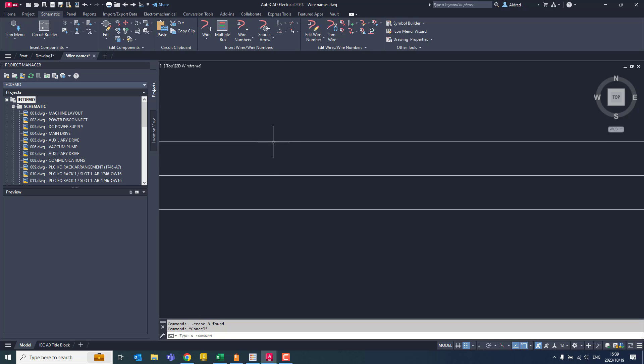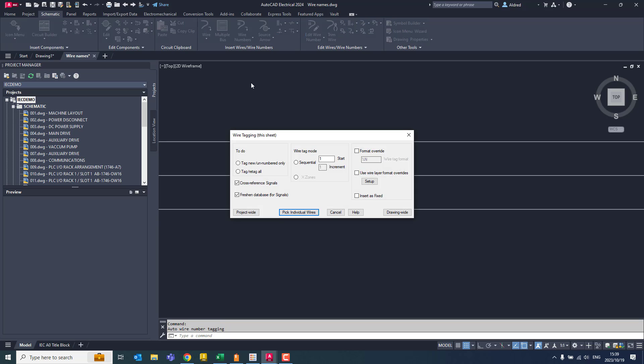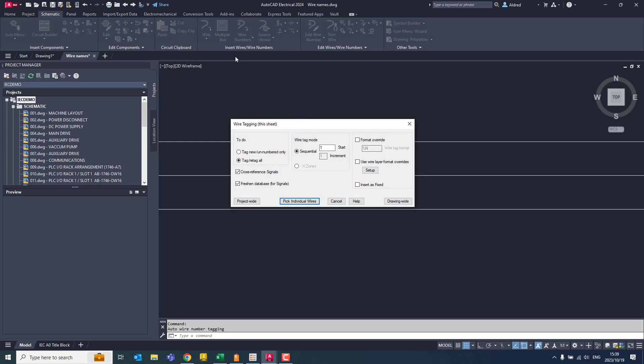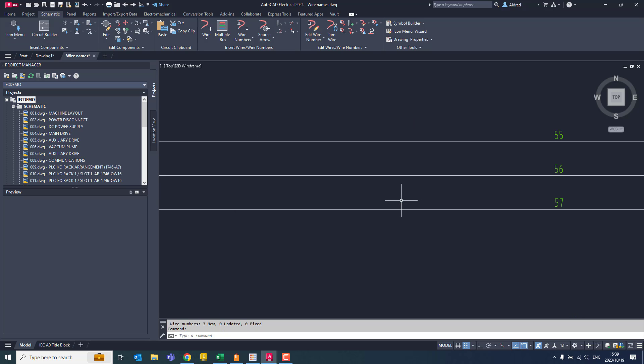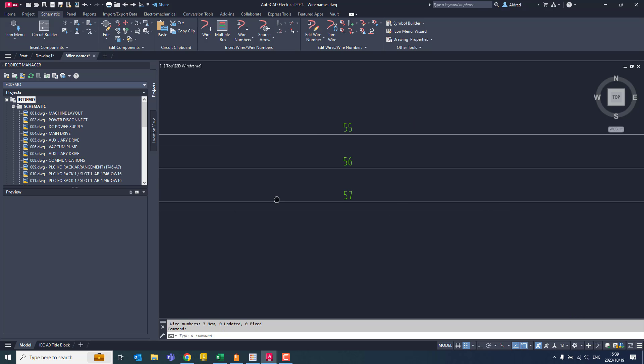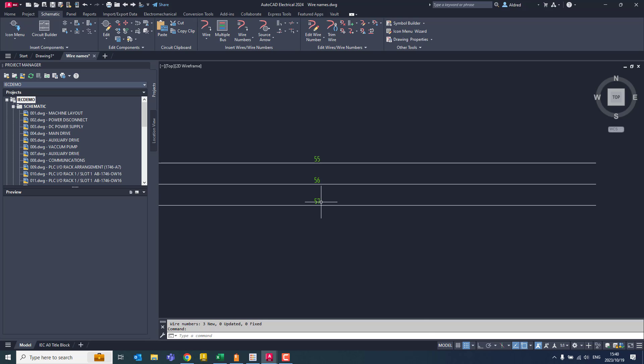Now with AutoCAD Electrical, we can automate the wire numbering process by clicking on wire numbers and doing a wire tagging. So with this wire tag, I'm just going to go say drawing wide and then tag all the numbers for it. So what it's done is it's also looked at all the other numbers in this project, and there I've got 55, 56 and 57.